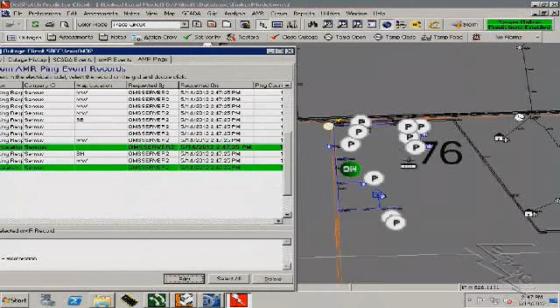Here's another example of a large outage showing all the meters calling in before we received a single phone call. This was 90 seconds into the outage, and 1,500 of the meters had already reported in without a single phone call. We also have remote devices at the substations called SCADA breakers that reported in that this outage was off.